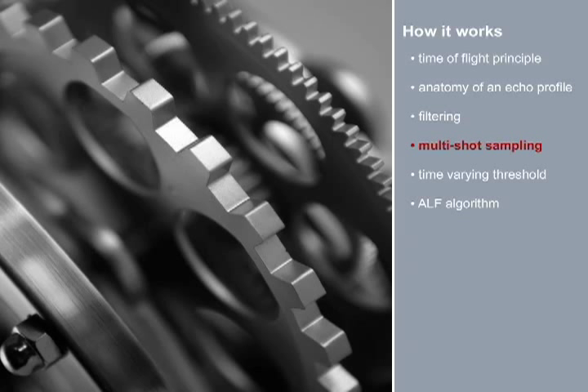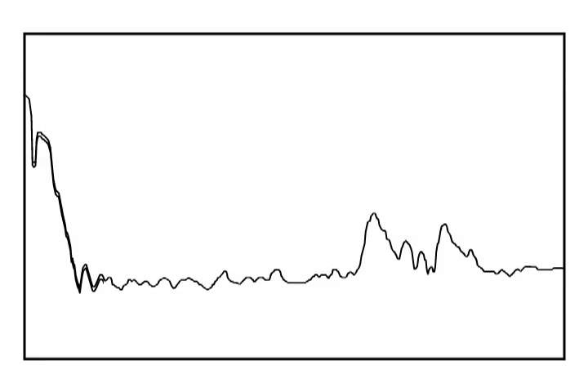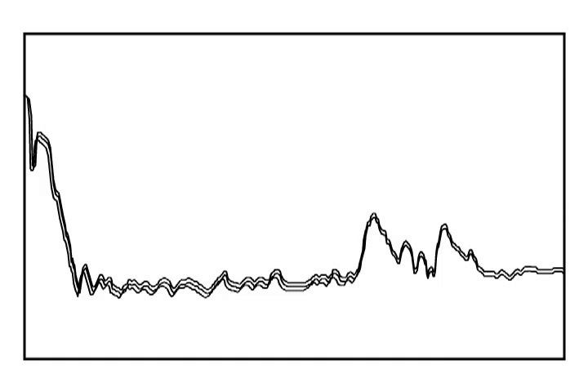Multi-shot sampling. The typical echo profile is not the result of one pulse. It is the average of a number of pulses. This is called multi-shot sampling. Each device has a different default value for the number of pulses or shots that it takes before processing the final echo profile.